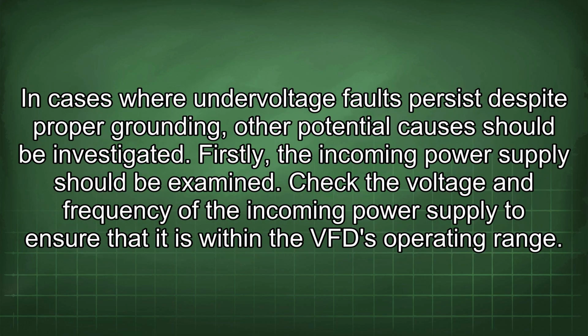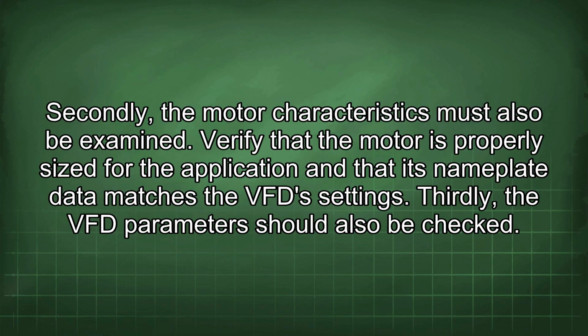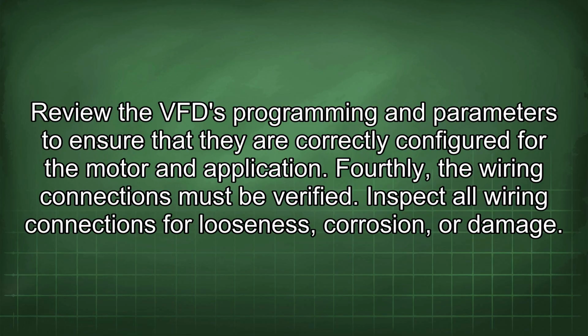In cases where undervoltage faults persist despite proper grounding, other potential causes should be investigated. Firstly, the incoming power supply should be examined. Check the voltage and frequency of the incoming power supply to ensure that it is within the VFD operating range. Secondly, the motor characteristics must also be examined. Verify that the motor is properly sized for the application and that its nameplate data matches the VFD settings. Thirdly, the VFD parameters should also be checked. Review the VFD programming and parameters to ensure that they are correctly configured for the motor and application.